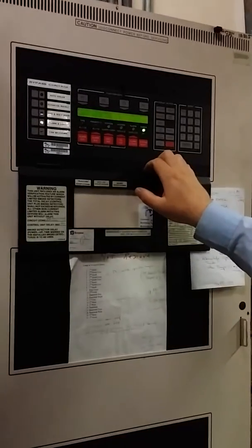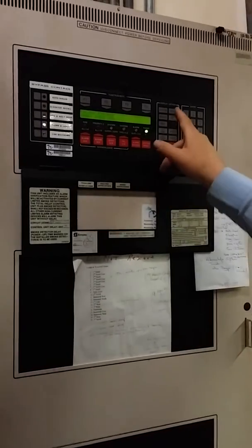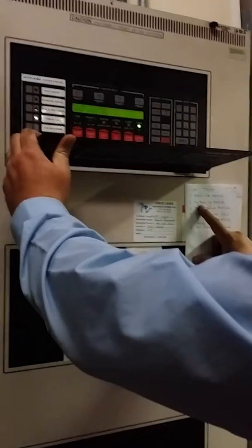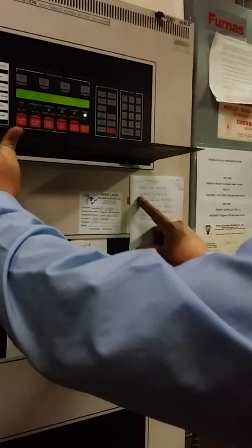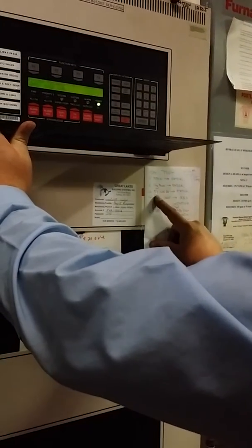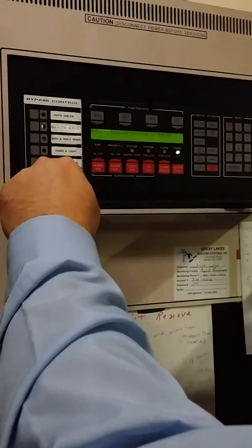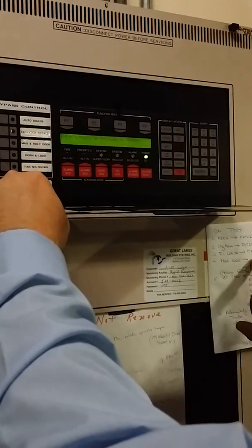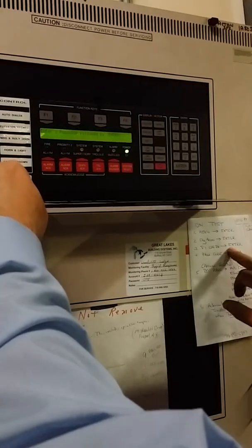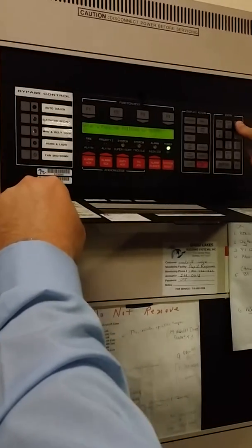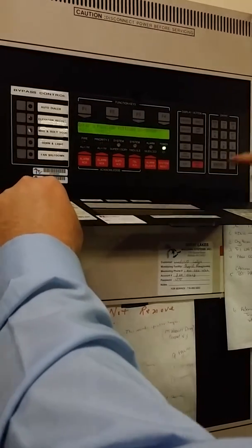So first it was panel, then change access level. Menu. Menu. Right here. If you got any questions. Change menu. Enter. Change access. Enter. Okay. F1 to log in, just like it's prompting you. The F1 up here, and then passcode 333. It says enter after each one. You don't have to do enter after each one. 333. Enter. Access granted. Bypass.